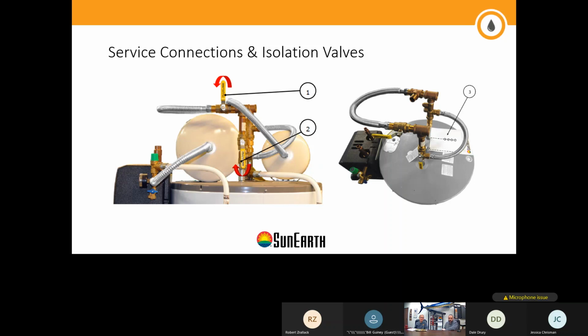So hot water stations are pre-plumbed, completely built solar storage tanks that have all the equipment that you need to operate the system already installed on it. Part of that equipment that we want to include is a bypass assembly. The bypass assembly allows the tank to be completely isolated from the potable water loop. The potable water will still flow freely from the main to the auxiliary unit, whatever it might have been.